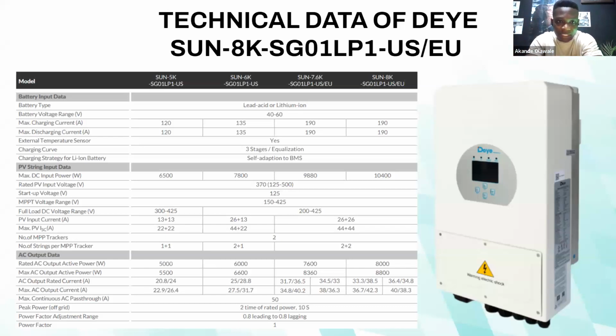Startup voltage on the PV side: you have close to 6,500 watts for the 5 kilowatts, and for the 8 kilowatts you have close to 10,400 watts. That's how much power you can actually put on these, which is really, really much.